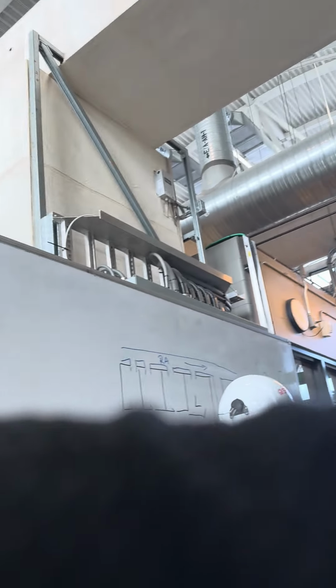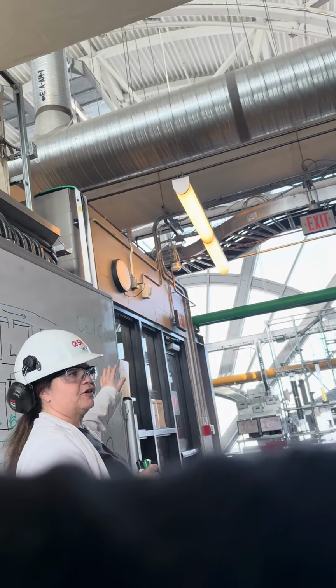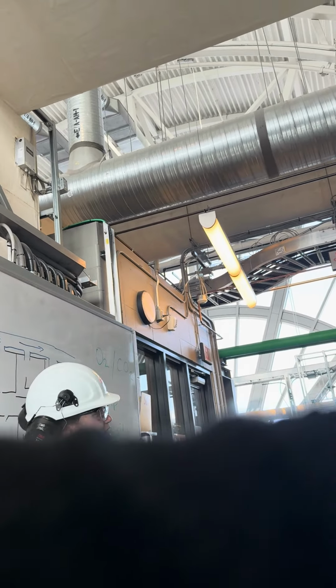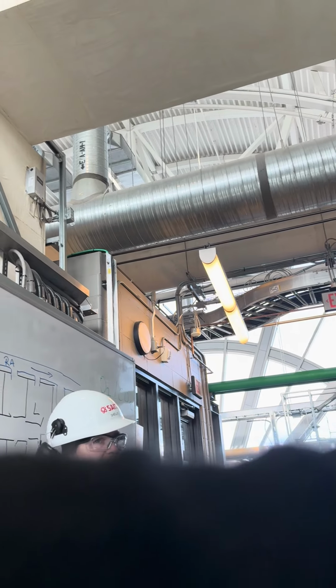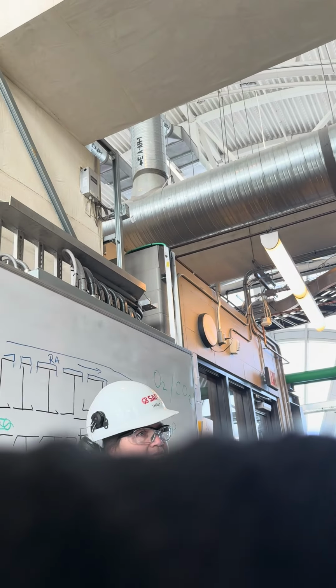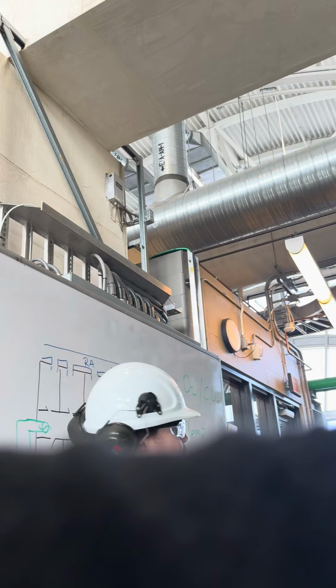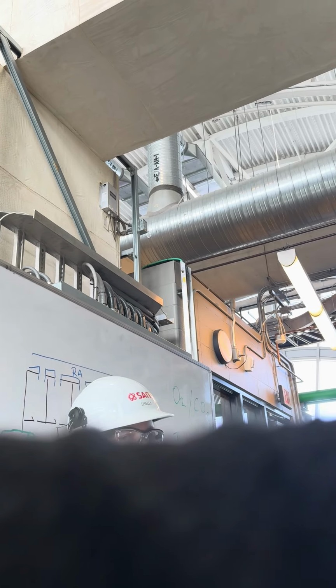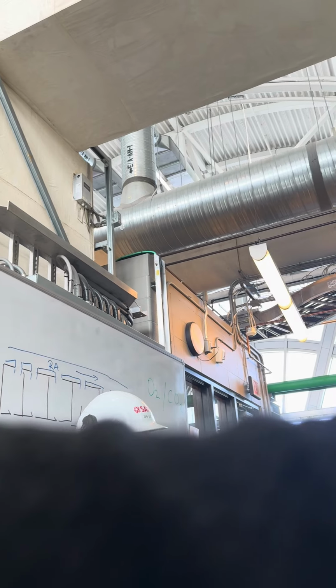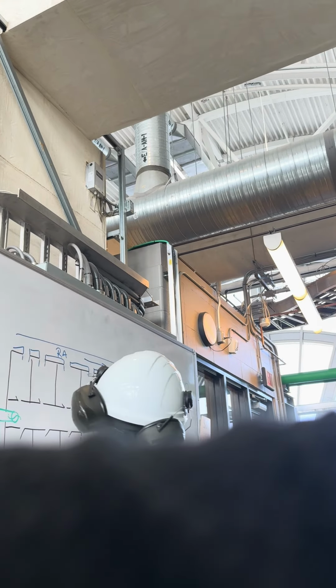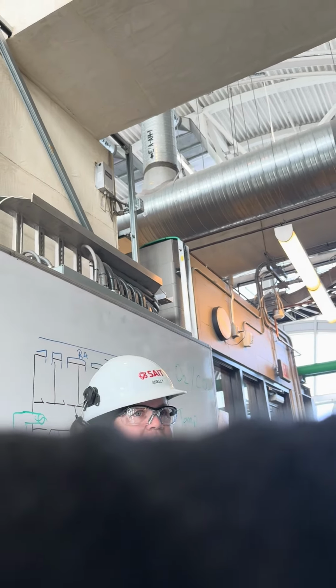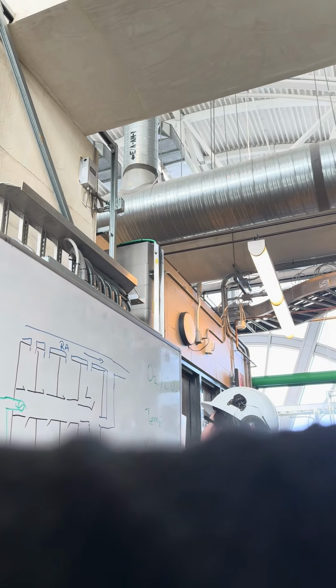Particulate - we're filtering out all the chunks. Now notice we're not actually killing any bacteria or eliminating smells, we're just filtering the air. If we wanted to eliminate bacteria and smells, we'd probably have charcoal filters, and you wouldn't have a recirculation of your air - it would be 100% supply air, because your return air goes back to your system.